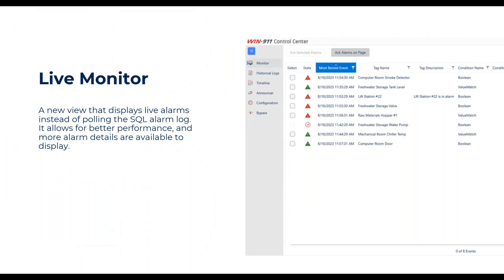The first thing I wanted to talk about was the live monitor. This is what shows you what alarms are active in your WIN-911 system at any given time — these are the actual live alarms currently in the system. If you used the log viewer before, that tool was just querying a SQL Server database and showing you the results. It was never really meant to be used that way and it was pretty slow, so it's been overhauled to give us this live view of alarms, which makes remote monitor windows much easier.